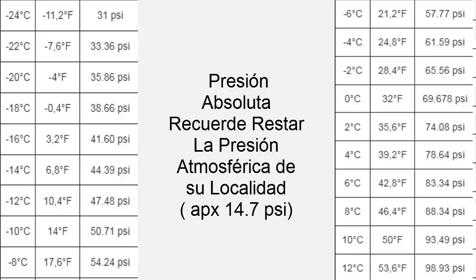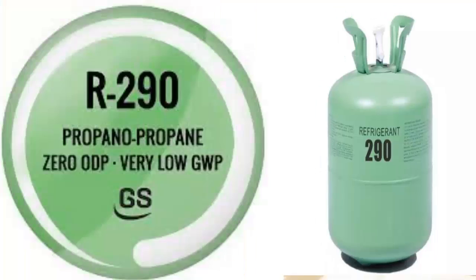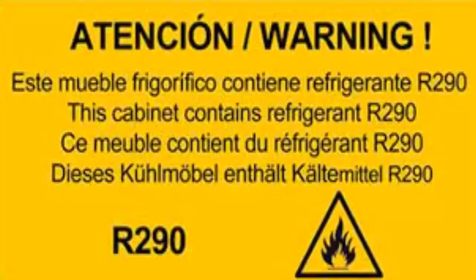The main drawback of R290 is its classification as a flammable refrigerant. However, as the refrigeration equipment where it is used does not have such high refrigeration capacities, and R290 has a significant cooling capacity, small commercial equipment requires very little R290 refrigerant, reducing the risk significantly.